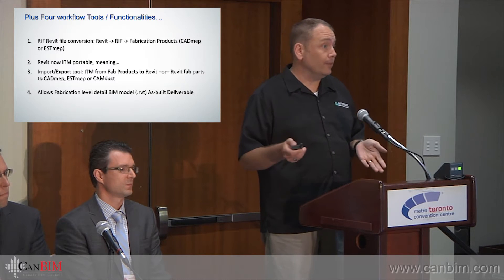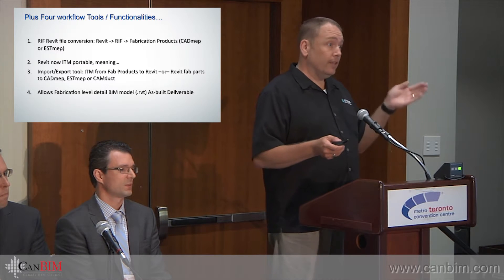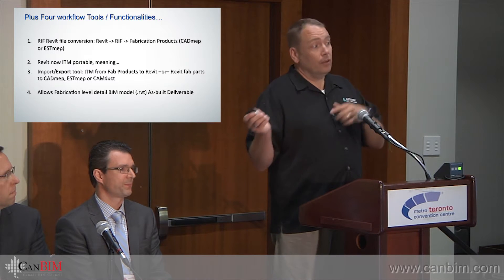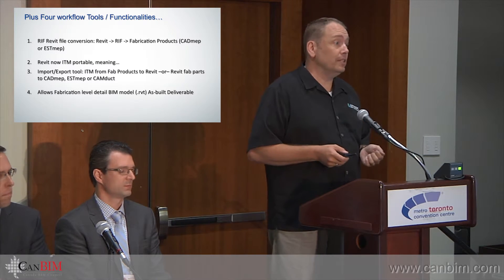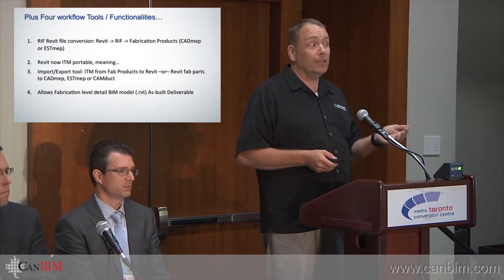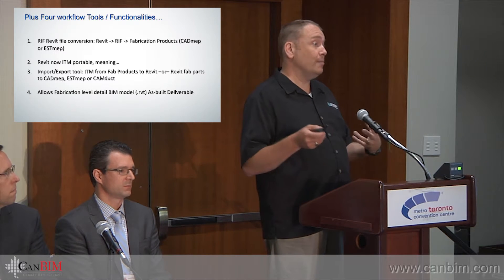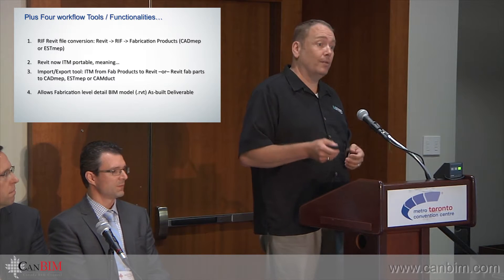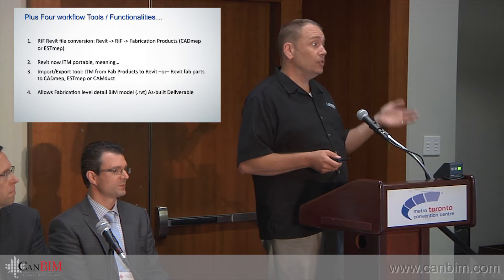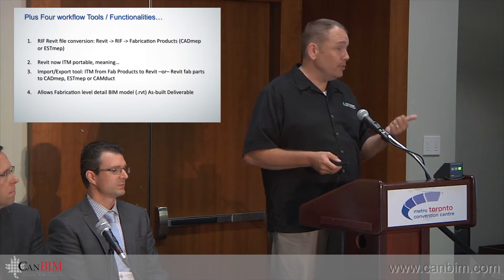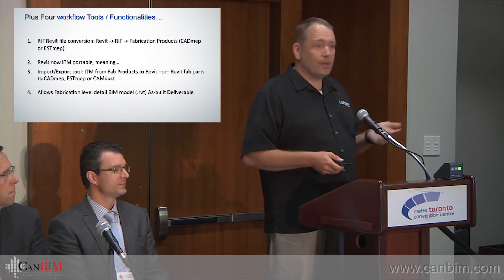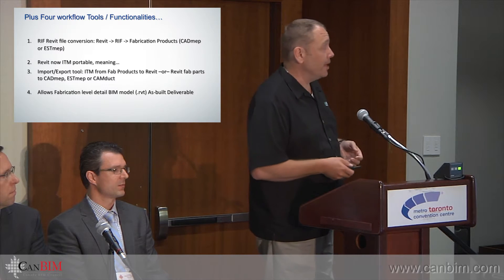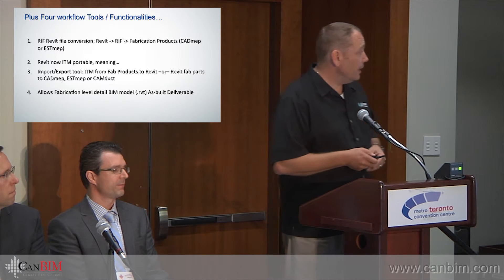So let's say you get a Revit project, convert out the RIF file, do all the fabricating you want, and the owner wants a fabrication-level detail BIM deliverable back. You simply use the export tool and take the geometry out of CADMEP back into Revit. In the Revit file, you save it as your as-built, delete all the ductwork and piping in between the equipment, and bring in the fabrication-level detail ductwork from CADMEP or ESTmep. The owner gets a fabrication-level detail hybrid Revit file with some Revit geometry and some fabricated geometry. You leave the equipment as-is because it has all the metadata about equipment changes and reordering parts.